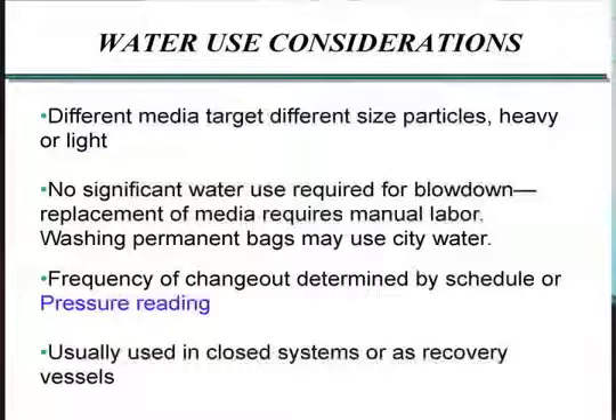There's many different ways to determine how to change these out. When I discussed my slides, I highlighted what is probably the most water efficient. These can be done manually or on a schedule, or can be changed out based off of a pressure reading. The thought is, if you're reading a pressure across that, you will know when that filter is loaded up and when it needs to be thrown out, so why do it more often than you need to? So my general recommendation is that this sort of system should be monitored with a pressure reading across the filter. Generally, these are used in closed loop systems and not often in open loop, although on occasion you'll see them there.